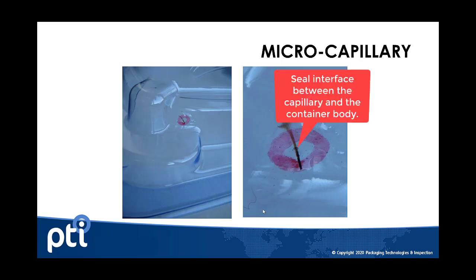You may ask how we know we're not introducing more leakage around the capillary itself as it's inserted and glued. You can validate that by placing glue on the tip of the capillary and proving that the container still remains leak-free when both the capillary is glued in place and the tip of the capillary is glued.